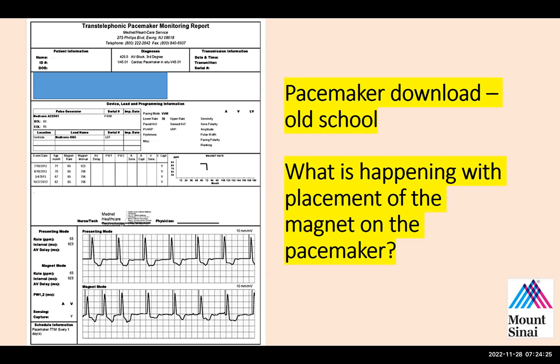Today, when you place a magnet on a pacemaker, in almost every case it causes the pacemaker to pace asynchronously in either DOO or VOO mode. Sometimes during surgery, anesthesiologists place a magnet on the pacemaker so that electrocautery artifact doesn't cause over-sensing and lack of pacing. The downside is that in asynchronous mode, if the patient were to have a PVC, you could have an R-on-T phenomenon and induce VF. We generally prefer not to leave somebody in asynchronous pacing mode. When you place a magnet on top of a defibrillator, it will typically deactivate the defibrillation feature. That's very important — for example, in an ER receiving inappropriate shocks from a broken lead, the ER doesn't need a programmer to deactivate the defibrillator; they simply place a magnet over the device.